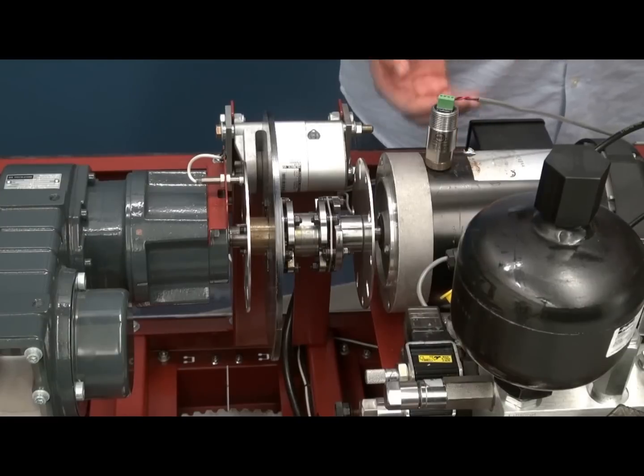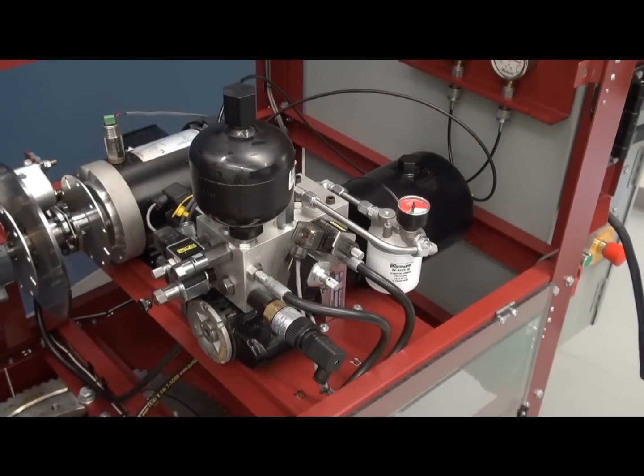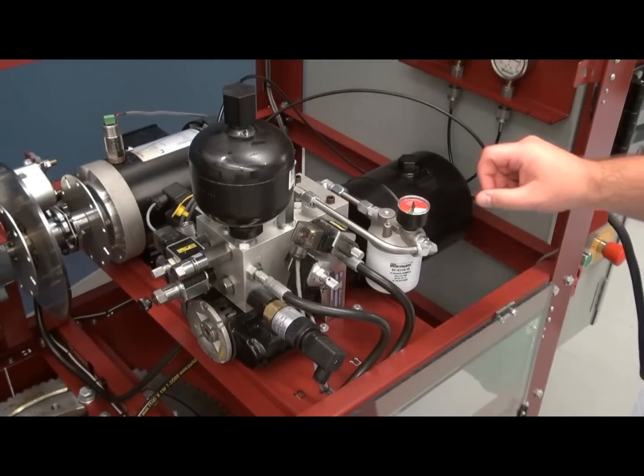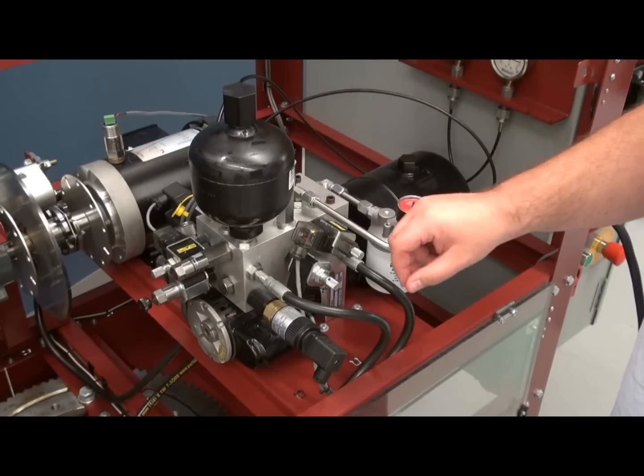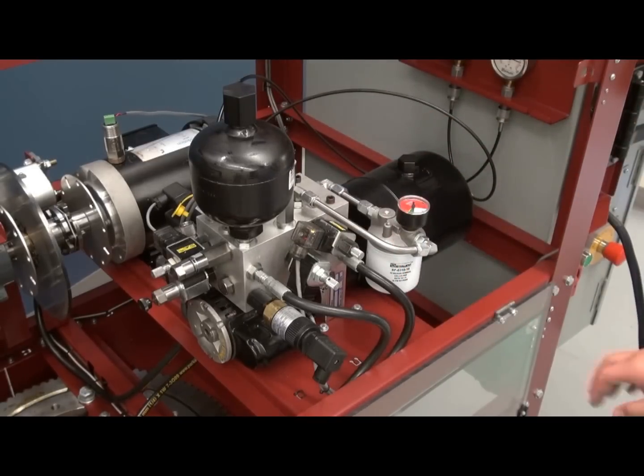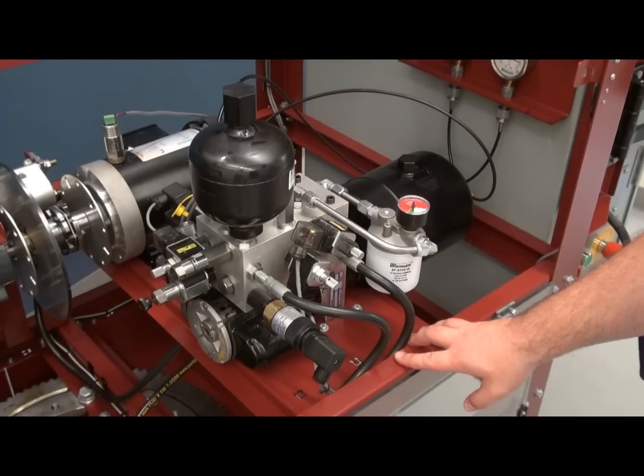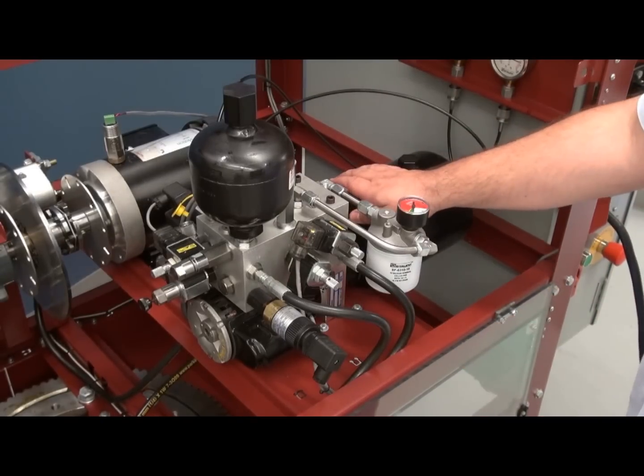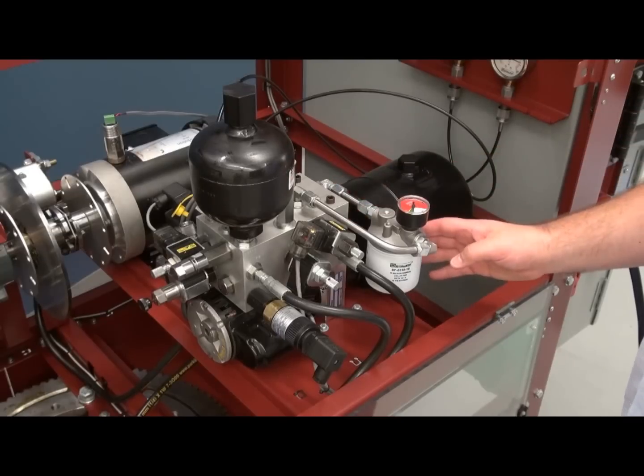As in an actual wind turbine, we also have a hydraulic unit which is normally custom made for each turbine. We have different kinds of hydraulic components like valves, check valves, relief valves, and an accumulator for emergency braking in case we lose power in the nacelle. Each of these valves can also be manually activated for troubleshooting or activated through the PLC. We also have a hydraulic tank and filter.